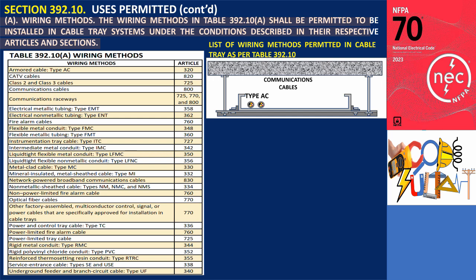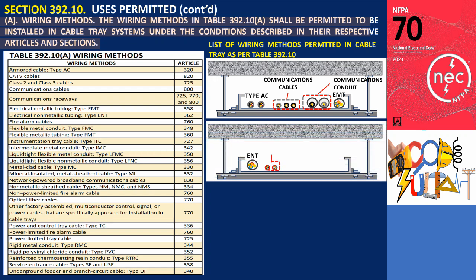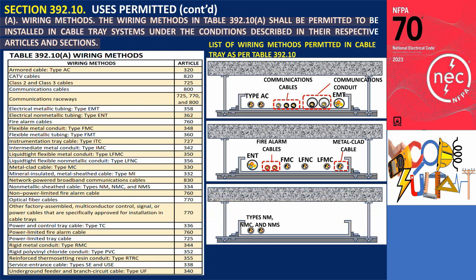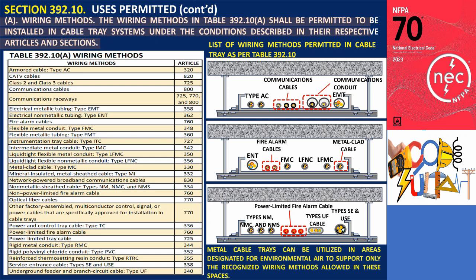The table includes: Armored Cable Type AC, Communications Cables, Electrical Metallic Tubing Type EMT, Fire Alarm Cables, Flexible Metallic Conduit Type FMC, Liquidtight Flexible Non-Metallic Conduit Type LFNC, Metal Clad Cable, Non-Metallic Sheath Cable Types NM, NMC, and NMS, Power Limited Fire Alarm Cable, Type MC Cable, Type UF Cable, and Service Entrance Cable Types SE and USE. Metal cable trays can be utilized in areas designated for environmental air plenums to support only the recognized wiring methods allowed in those spaces. It is not the metal cable trays that impose limitations, but rather the specific cable or wiring method being used.